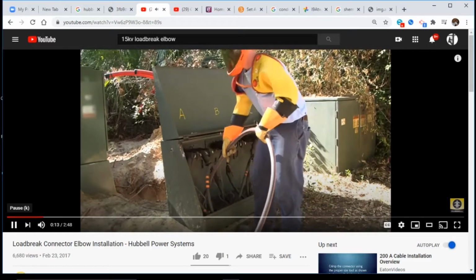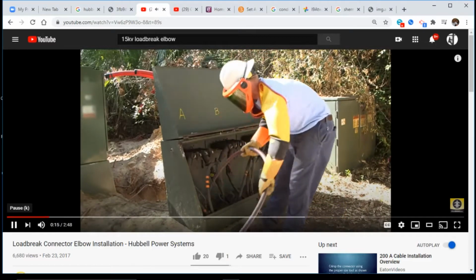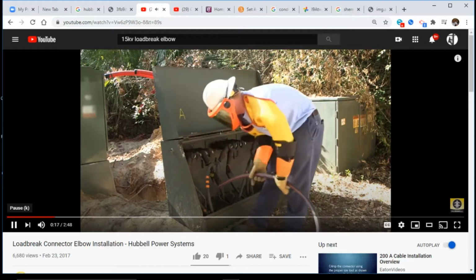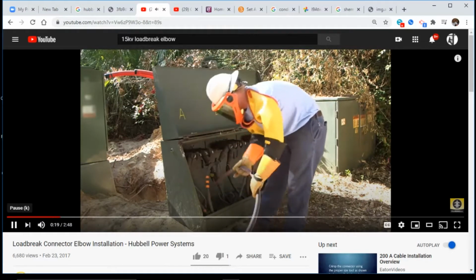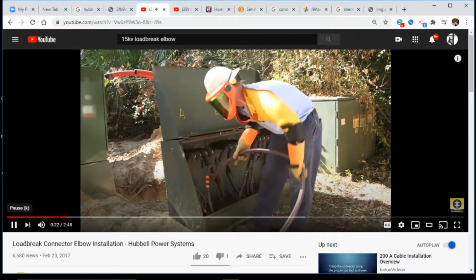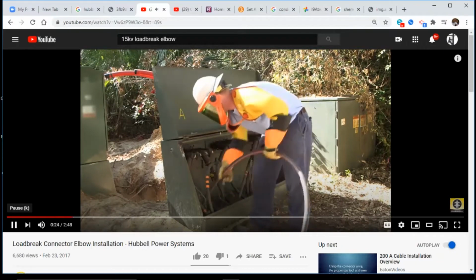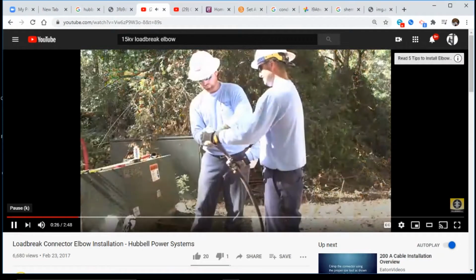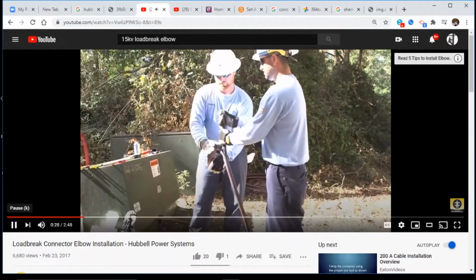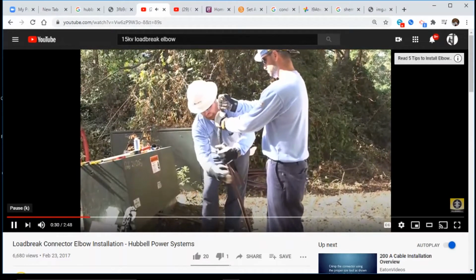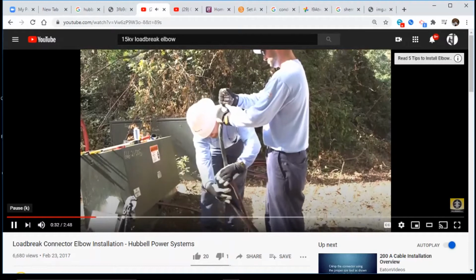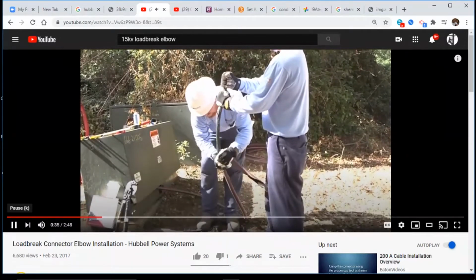Train the cable into the final assembled position per transformer cable practices. Allow sufficient slack in the cable to pull the elbow connector at least 1 foot away from and in line with the center line of the mating part during the load break operation. To provide sufficient length of concentric neutral conductor for grounding after installation, measure 8 inches down the cable from the center line of the bushing interface and remove the outer jacket to this distance.